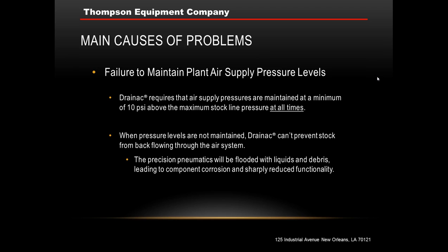Main causes of problems. Failure to maintain the plant air supply pressure levels. As I mentioned, Drainac requires that the air supply pressure levels are maintained at a minimum of 10 psi above the maximum stock line pressure at all times.